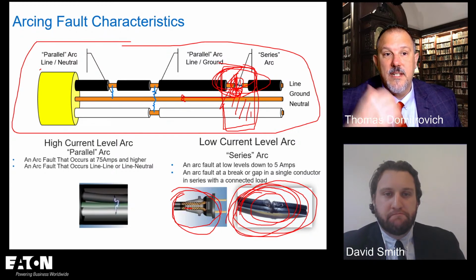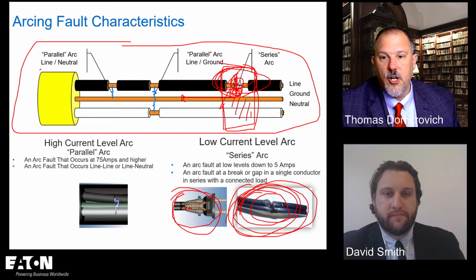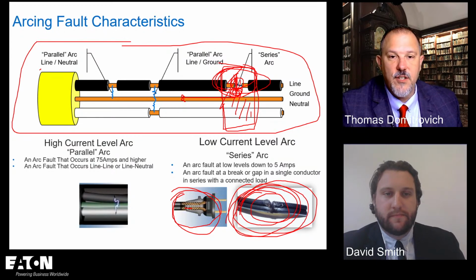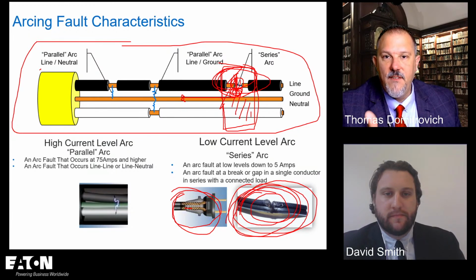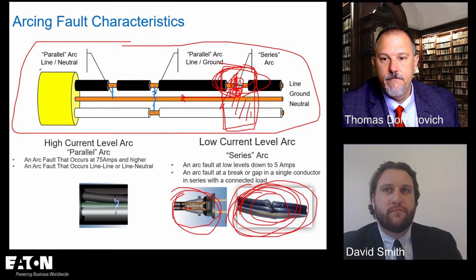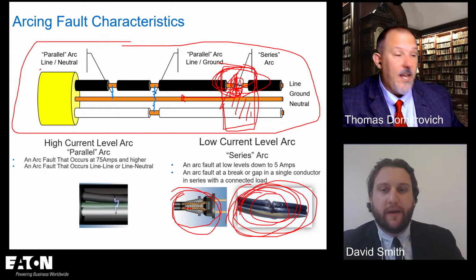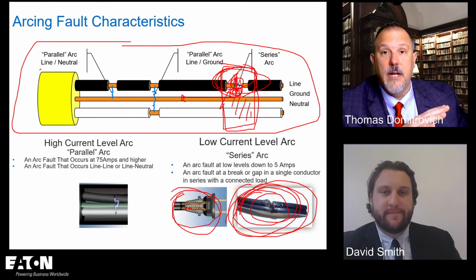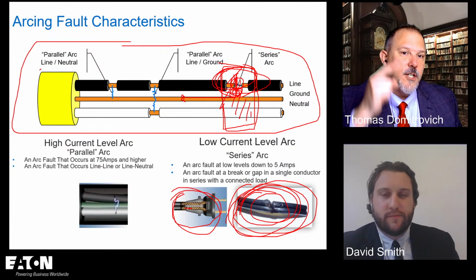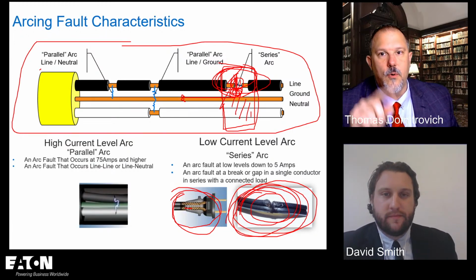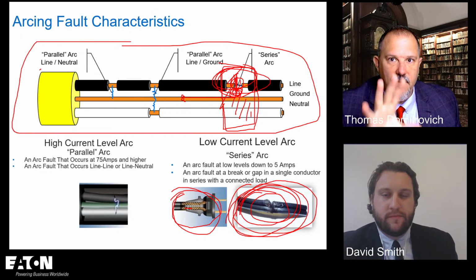So when someone says, what's the difference between a combination type AFCI and a branch feeder type AFCI? A combination type AFCI gets you 5 amp series arc testing on SPT2 cord. That's what it does. In addition to everything else that the regular one does, it gets you that one additional test on SPT2 cord, which is a series 5 amp arc.